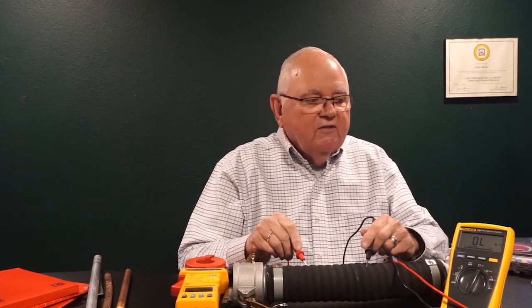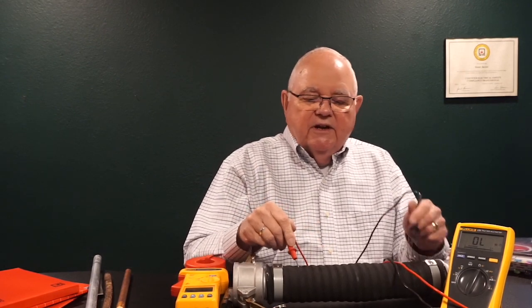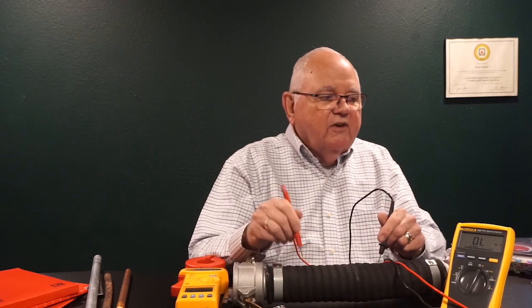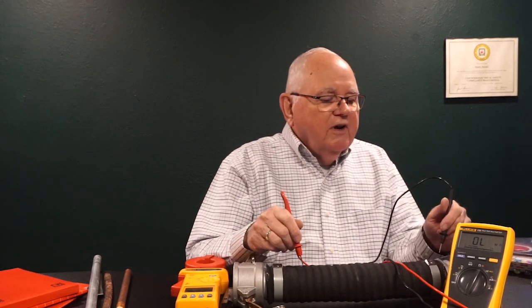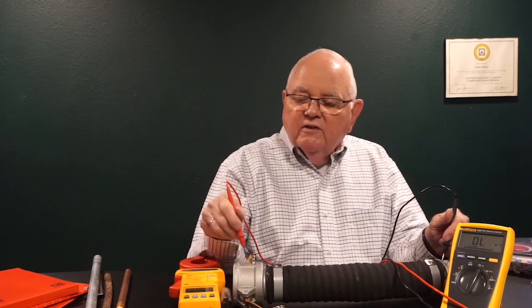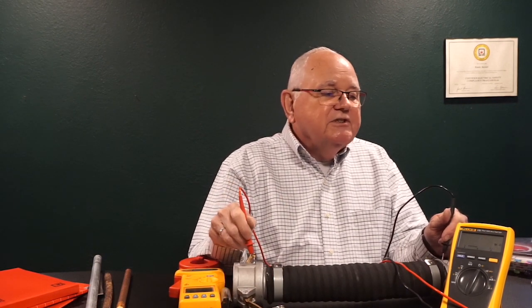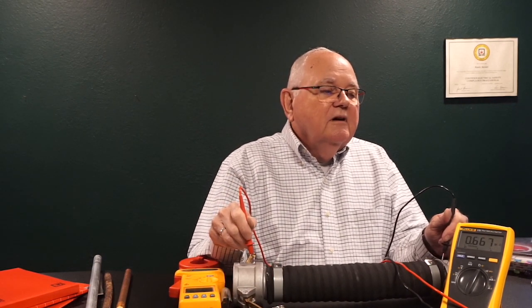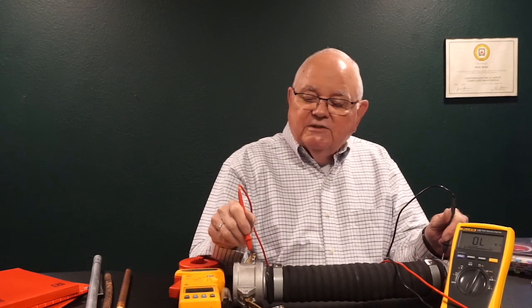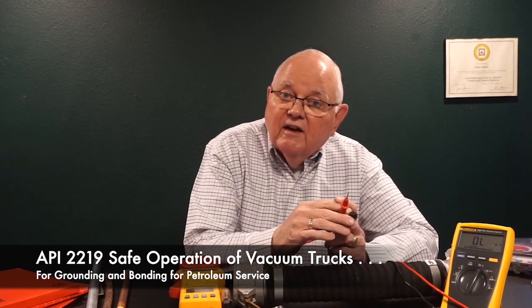And of course, if I try and read across the rubber hose, I get infinity, OL on my meter, right? Wherever I try and read across the rubber hose. Now, if I try and read from the metal on one end to the metal on the other end, I do get some resistance. I get continuity. It's not a very low resistance in this particular case, but it's okay. It meets the requirements of the American Petroleum Institute standard, the API standard, that governs vacuum truck operations. Very extensive information in that standard on vacuum trucks, and grounding and bonding of vacuum trucks.